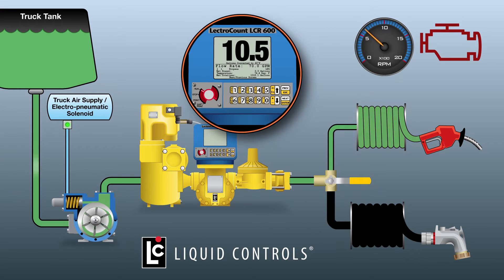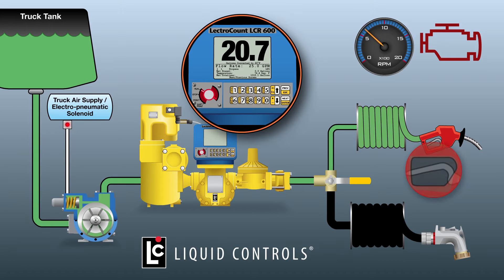The increased rate of fuel flow and gallons per minute show on the display. When the fueling process is nearly complete, pressure is slowly relieved on the nozzle lever. The LCR600 automatically deactivates the AOV on the pump, opening the bypass valve, which decreases the outflow rate of fuel from the pump. When the fueling process is complete, the nozzle lever is released to the closed position and the flow of fuel stops. The switch on the LCR600 is turned to the print position, and a delivery ticket is printed for the customer.